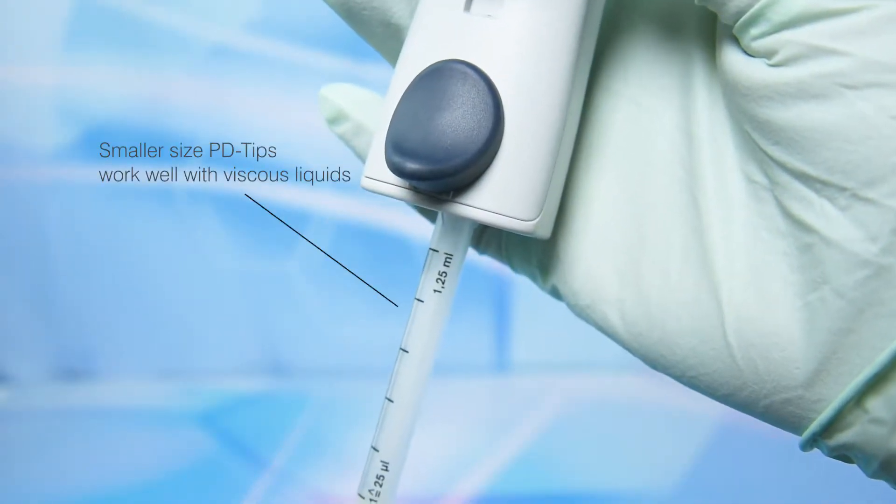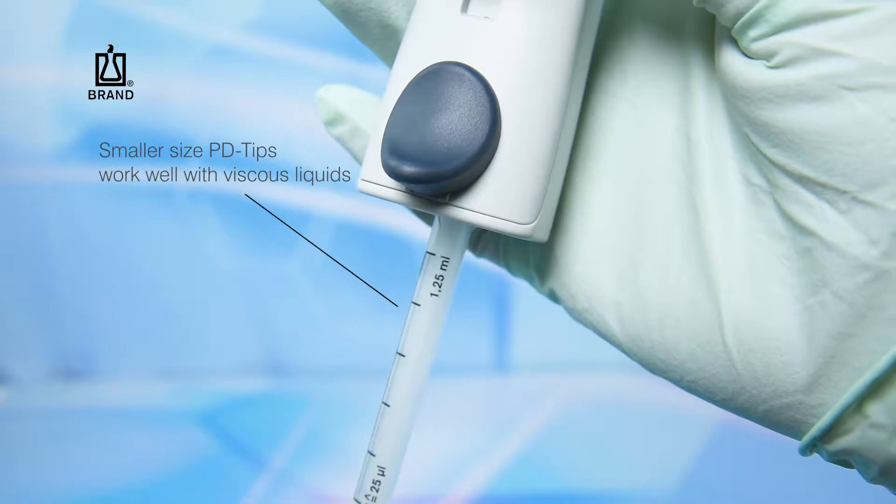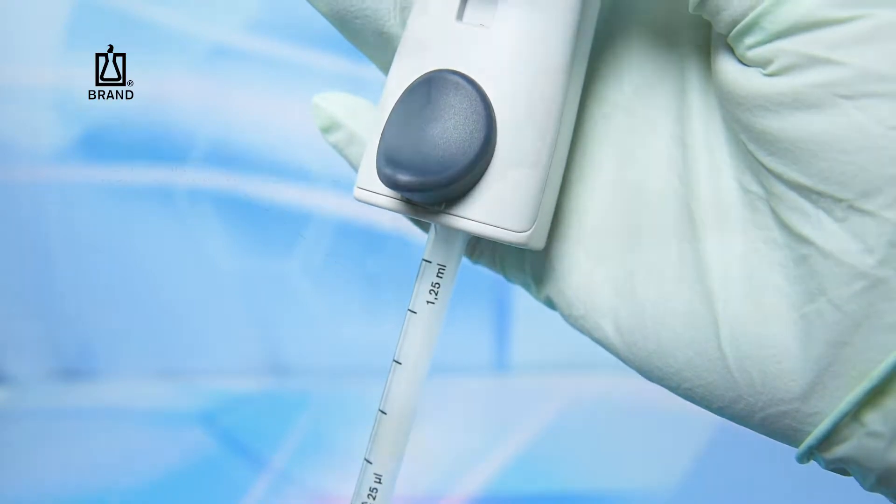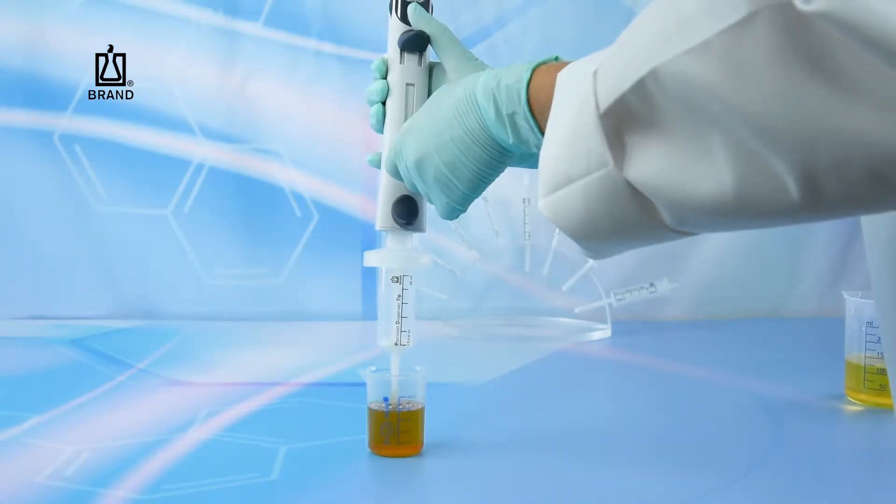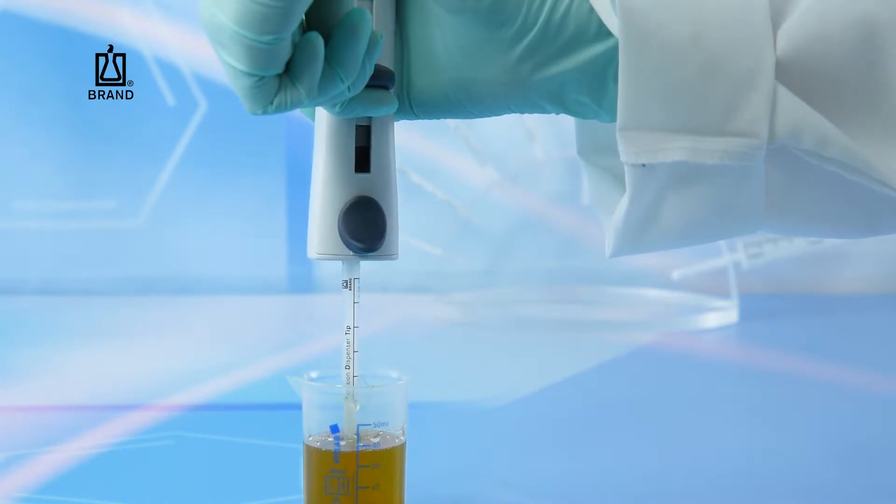You should note that smaller sized PD tips can deal with more viscous liquids than the larger ones. If a liquid is too viscous for a larger PD tip, you may want to try a smaller size.